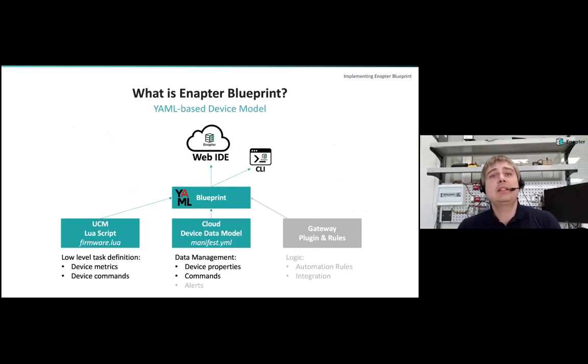The Enapter Blueprint is a bundle of files which are written in YAML and Lua languages. These files are used to declare possibilities of the integrated device. In our case, this is the air handling unit. The main part of the blueprint is a UCM Lua script. And it handles the low-level integration of the device with the UCM. This script handles Modbus communication as well as device-specific logic. For our example, it can be conversion of the floating point temperature into an integer number using the multiplier.